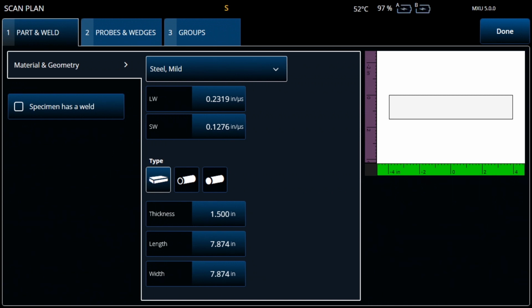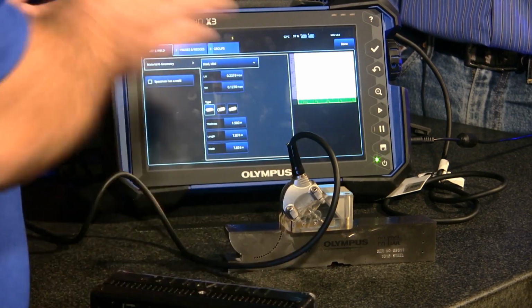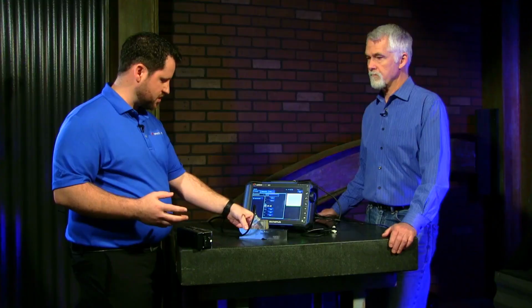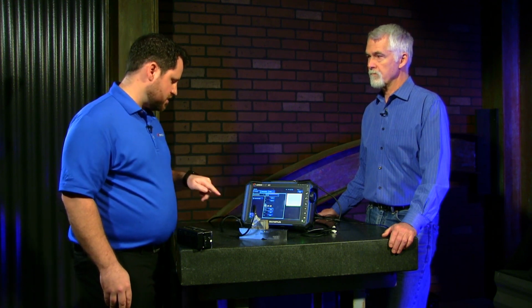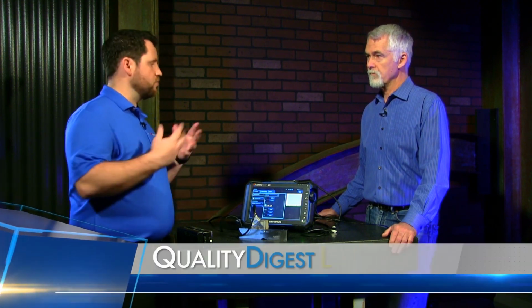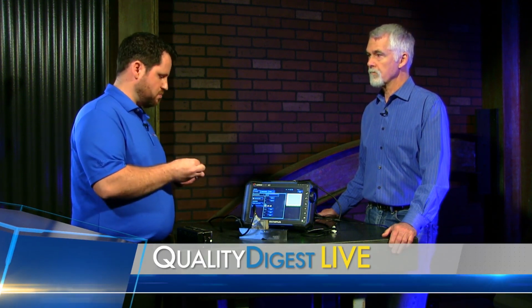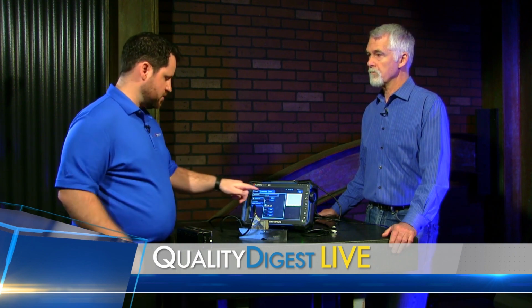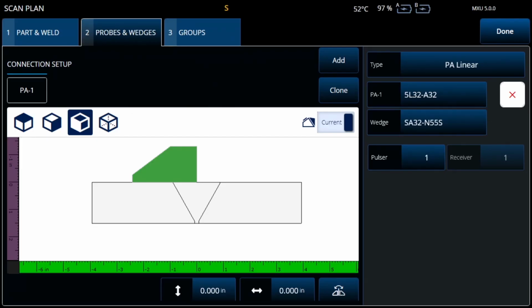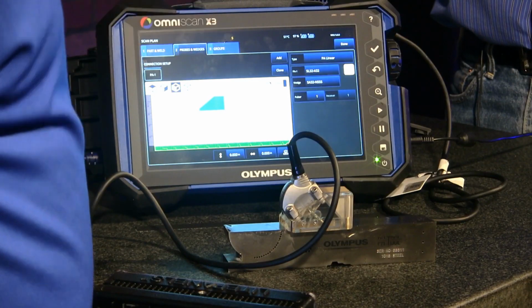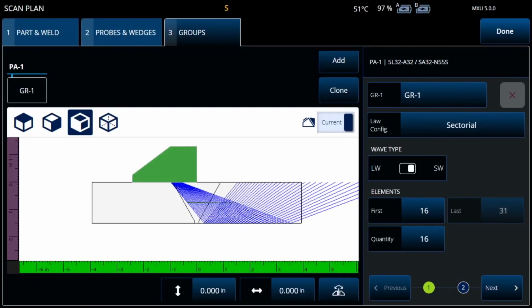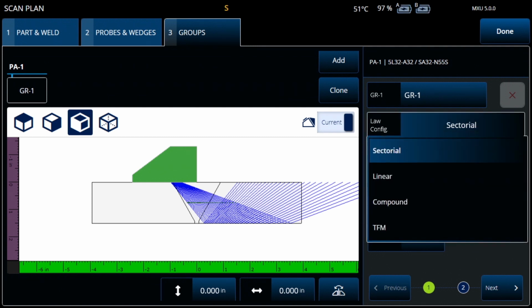Yeah, correct. Okay. So the technician here has access to all 3 phases of that setup portion, which is adjusting for the component that you're testing: material type, the thickness for the component, maybe even adding in what we call an overlay or an image of the internal makeup of the part so that we can better interpret the signals. And then an easy transition into the equipment that we're using, which probe and wedge you have selected, adding multiple different transducers for a more complex inspection, and then in the last step, switching over to what you want emitted from that transducer, what type of inspection you want to perform, whether that be standard sectorial scan, linear scan, compound scan, or switching into our new FMC TFM inspection.